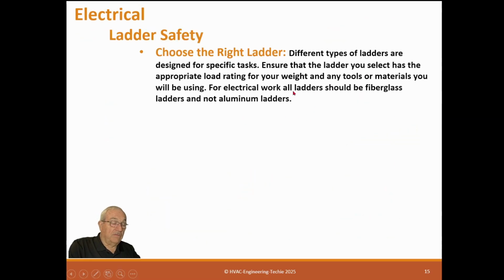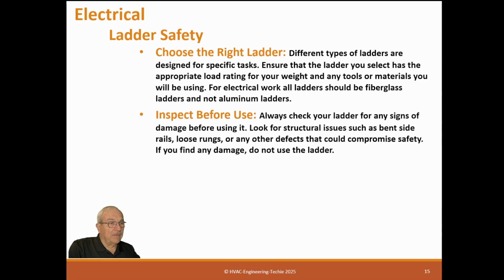Ladder safety, which is another safety issue. Choose the right ladder. Different types of ladders are designed for a specific task. Ensure that the ladder you select has the appropriate load rating for your weight and any tools or materials you will be using. For electrical work, all ladders should be fiberglass ladders and not aluminum ladders. They should be non-conductive, so in case you drop a live cable on it, it's not going to light up. Inspect before use. Always check your ladder for any signs of damage before using it. Look for structural issues such as bent side rails, loose rungs, or any other defects that could compromise safety. If you find any damage, do not use the ladder. The ladder needs to be discarded.